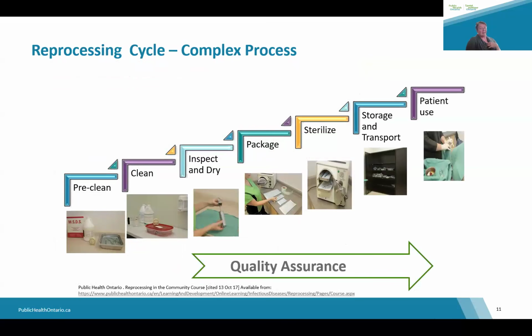Now, this is one of my favorite slides because it shows the reprocessing cycle, and it shows, I think, how complex it is, because many people think that reprocessing is very simple. It's just cleaning and sterilization of instruments. How hard can that be? Well, in reality, this process is very complex and becomes more so as instruments become more complex. So this slide outlines the basic steps of the reprocessing cycle. First, we have pre-cleaning at point of use. So this is the removal of proteinaceous material so it doesn't stick to your instrumentation. And if you can't clean it right away, then it needs to be kept moist, because if the proteinaceous material sticks to your instrumentation, then it's really hard to get off.